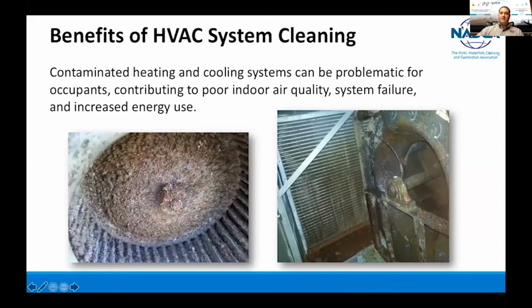Contaminated heating and cooling systems can be problematic for occupants, contributing to poor indoor air quality, system failures, and increased energy usage. This photo here on the left side of the screen is a blower wheel. The blower wheel has accumulated, due to airflow, some kind of microbial growth, and it's continuing to grow. And what happens is within the blades there, it reduces the efficiency for air to pass across a heating or cooling surface. So if you're reducing the air that this system is supposed to be producing, you increase the likelihood of a system failure.